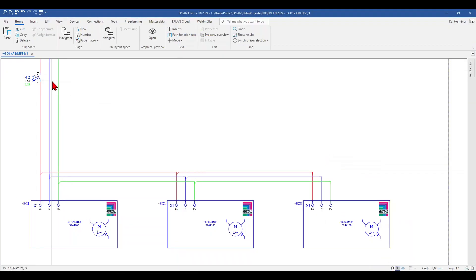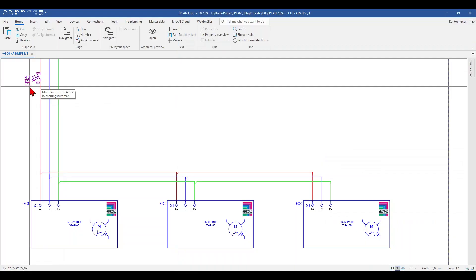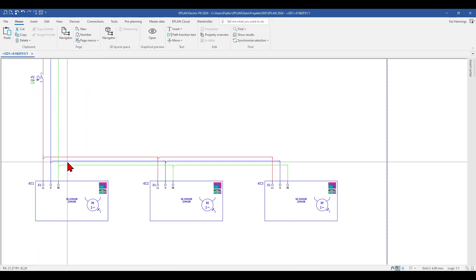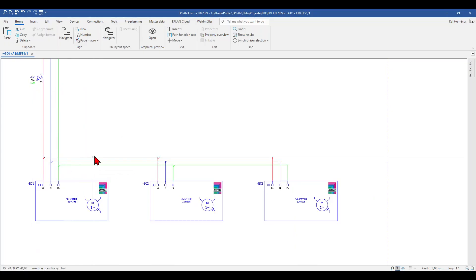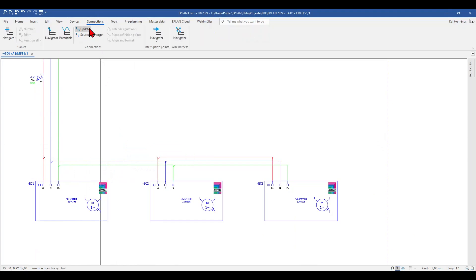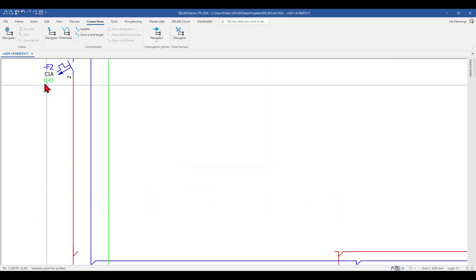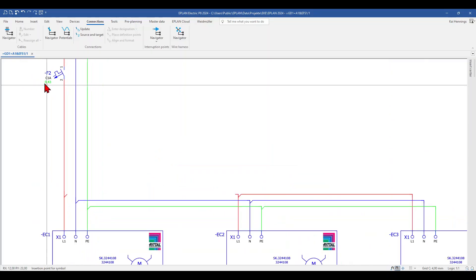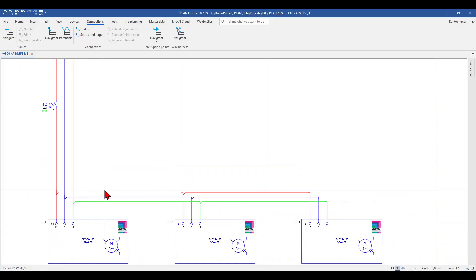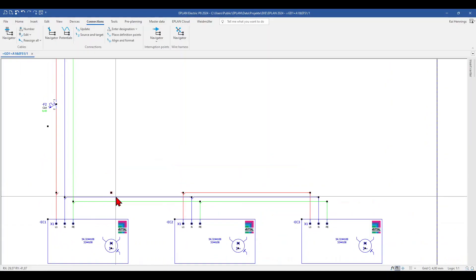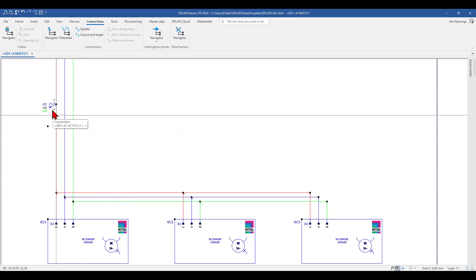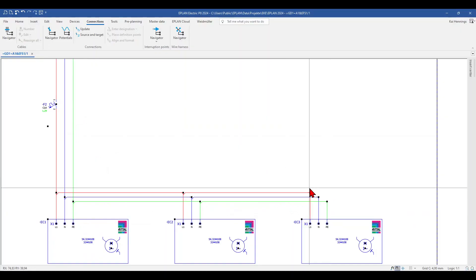Because we added on the tab view already the block property 1, you can see the total current here. When I interrupt a connection — for example this one — go to connection and update, you can see that the value changed to 0.43A, which is the current of one device. So when I delete this interruption and update the connection, we have the total current of all three of them.